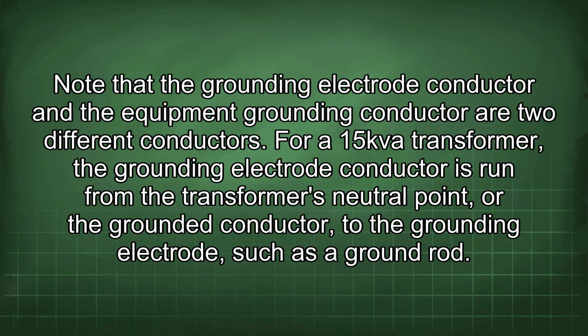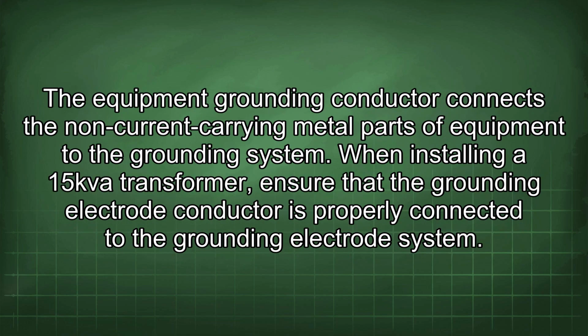Note that the grounding electrode conductor and the equipment grounding conductor are two different conductors. For a 15kVA transformer, the grounding electrode conductor is run from the transformer's neutral point, or the grounded conductor, to the grounding electrode, such as a ground rod. The equipment grounding conductor connects the non-current carrying metal parts of equipment to the grounding system.